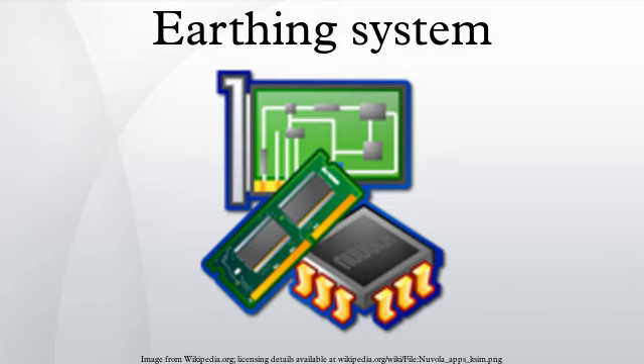The conductor that connects the exposed metallic parts of the consumer's electrical installation is called protective earth. The conductor that connects to the star point in a three-phase system, or that carries the return current in a single-phase system, is called neutral. Three variants of TN systems are distinguished: TN-S, where PE and N are separate conductors that are connected together only near the power source. This arrangement is a current standard for most residential and industrial electric systems, particularly in Europe.